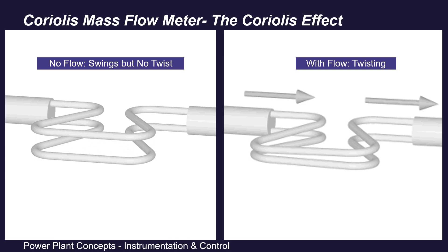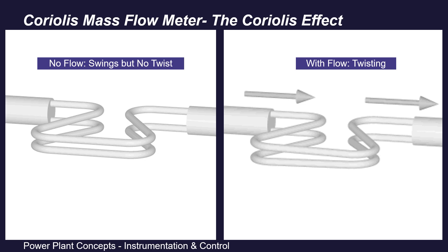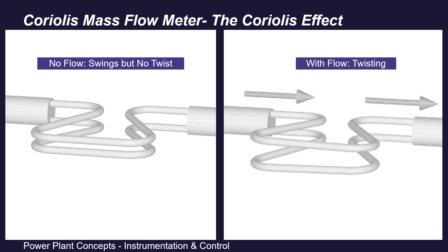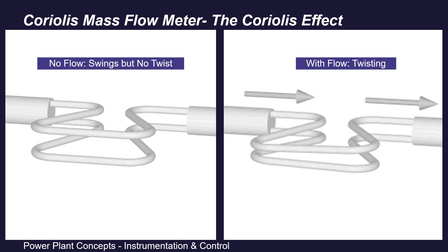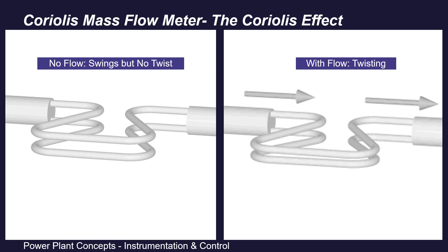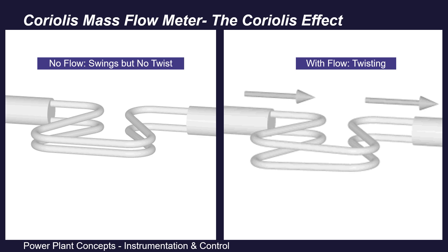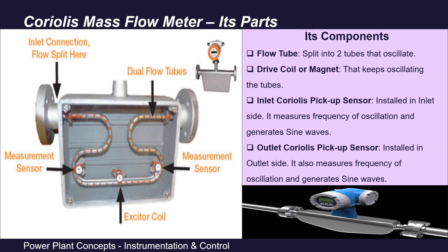Similar to the hanging pipe example, the tubes in a Coriolis flow meter also twist when fluid is flowing through them. However, the swinging effect in this case is generated by magnetic repulsion. The tubes are magnetic in nature and a same-polarity magnet — called the drive coil — is installed in the flow meter. The magnet and the tubes repel each other, and the tube tends to regain its original shape, causing the tube to start swinging.